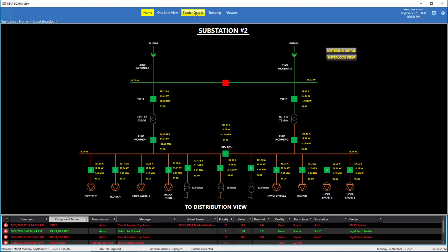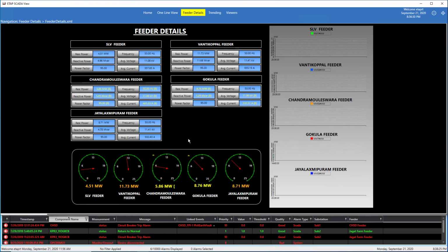As I mentioned, you have the ETAP HMI Designer, so you can create as many of these presentations as required. Notice that there is a lot of very flexible configuration. Users, depending on their standards, can create templates designed to reflect the data. There are a lot of capabilities, including data quality. In this case, we see some measurements with a letter B, meaning bad quality of information, so the operator or the substation manager can easily see what data is in good quality and bad quality.